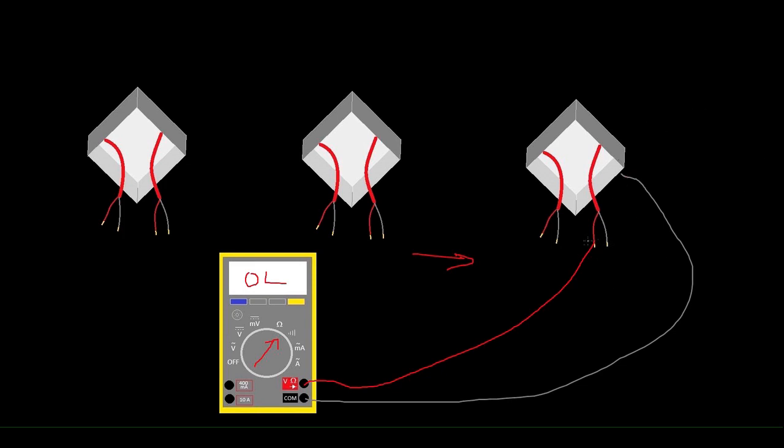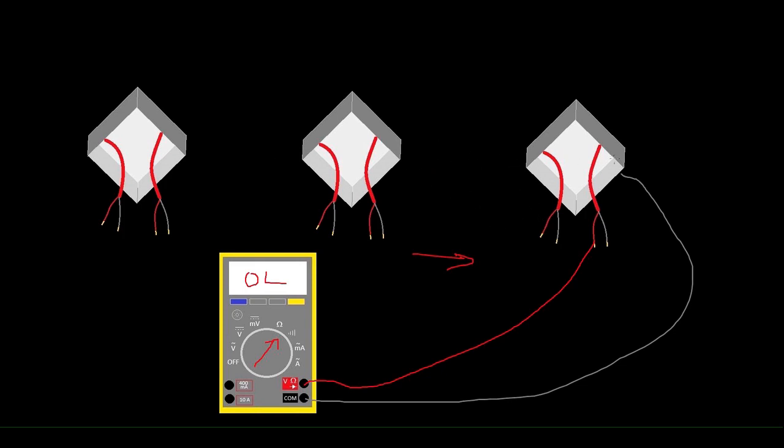Now one thing that will change is when you do meter your ground fault, it's not going to be 3.2, it's going to change in every spot you're at because what you're metering is the continuity to ground, the resistance to ground. And so the closer you get to the actual ground fault, the lower or closer to zero that number is going to get. So if you were to just take your red and black meter leads and touch them together, you're going to get like 0.1 ohms. If you were to meter, I'm just making this number up, let's say you meter a 20 foot wire that's 14 gauge solid, maybe you'd get one ohm or something like that. As you do this more you'll start to know what those numbers mean. So if you had 10 ohms to ground, your ground fault's a pretty good distance away. But if you had two ohms to ground, you know you're pretty close to it, and so you'll just kind of work your way whichever direction it's taking you.